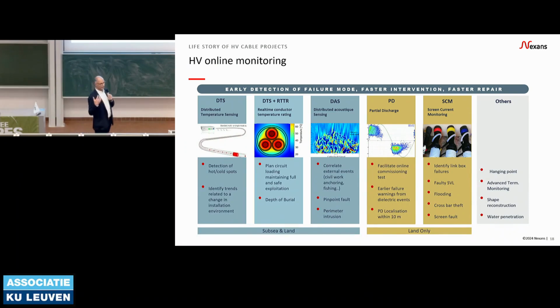We can use the optical fibers inside the cable to monitor temperature and vibrations. We can also use partial discharge devices, HFCTs, high frequency current transformers, to measure partial discharge on the cable accessories. We can also check the screen current in the screens, just to see if something is happening there.